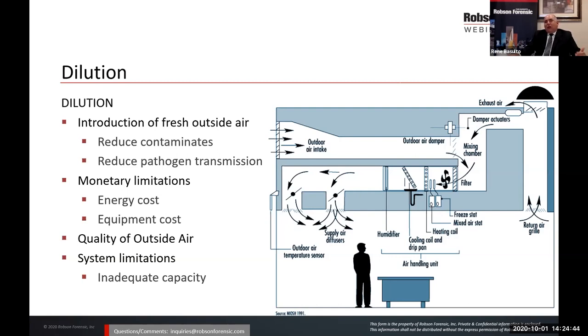In that particular space, we were maintaining negative pressure in the quarantine rooms to ensure that nothing these animals are bringing in could be transmitted to the other rooms where the other animals were. So we're bringing in 100% outside air. We were exhausting all of it. We were making sure that the pressure differentials between the rooms were adequate, so that the air from one room would not pass into the other one.